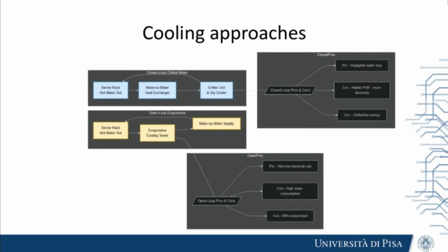We use a closed circuit. When you chill things down, you basically have two options today. One is a closed loop of water—you chill down the water, maybe use adiabatic cooling if you're smarter, but it's still a closed loop, so you fill the tank with very little water dispersion. There's a lot of issues with the kind of water and keeping it clean, because circulating water can cause problems—but that's fine for the design we made.